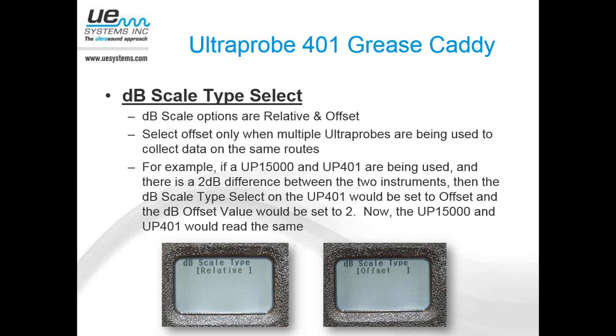In the next scenario, you will get different decibel level readings. Let's say you're using the magnetic mount contact probe on the 15,000 and then you're using the magnetic mount of the 401. You may get a difference of 1 or 2 dB between the 2 instruments. So if you wanted each instrument to read the same, or to match up, you would come here on the Ultraprobe 401 and change the dB scale type from relative to offset. And then the next menu that we'll talk about is the dB offset value. You would go into that menu and enter 2 if they were reading 2 dB apart.